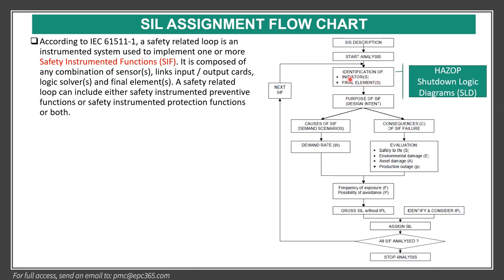Normally we define the SIF from HAZOP or from the shutdown logic diagram. When you find your SIF, you have to define its purpose, then identify the causes of the SIF, which can be called the demand scenario. For each demand scenario, we have a demand scenario rate. Then we have to do the safety risk graph, which comes from IEC and is sometimes calibrated by companies for their own system. The risk graph covers safety to people, environment, asset, and production.